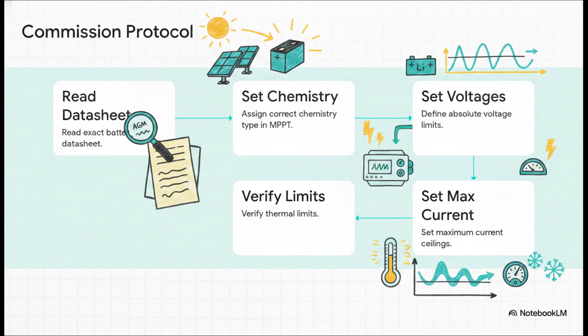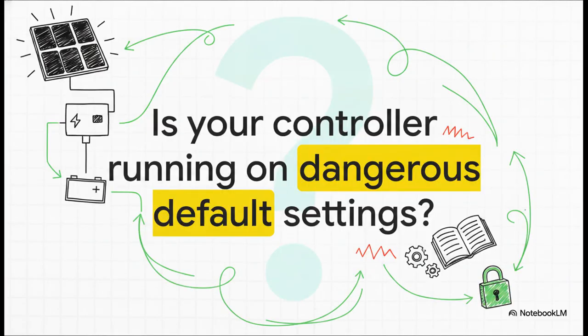You absolutely must read your exact datasheet, manually assign the correct chemistry type, define your absolute bulk, absorption, and float voltages, set your max current ceilings, and always verify your thermal limits. Which leaves us with this one vital question. Right now, today, is your controller running on dangerous default settings? I highly encourage you to pull out your system's manual right after this explainer.